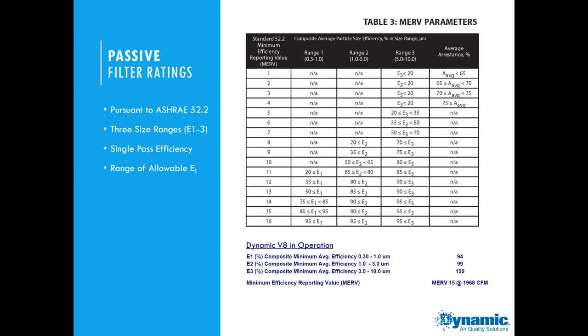That said, what it does is it takes your worst performance in each size category, averages those together, and gives you your efficiency. So if you look at that chart and go down to the line 13, a MERV 13 filter is more than 50% efficient in the 0.3 to 1 micron range. It's more than 85% efficient in the 1 to 3 micron range, and more than 90% efficient in the 3 to 10 micron range.